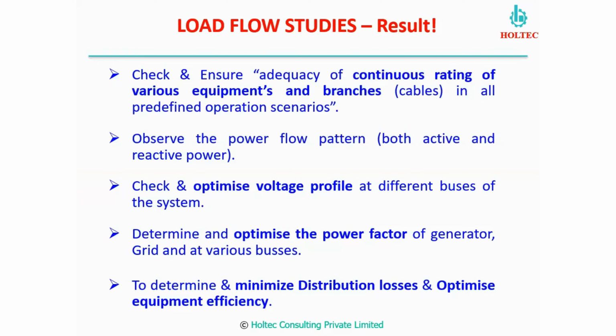Why is this voltage profile optimization required? Actually speaking, with higher voltages the fixed losses increase, because we have mostly inductive loads, whether it is a transformer, a generator or a motor. In inductive loads, the fixed losses or iron losses are proportional to the square of the voltage. So the moment we increase the voltage to its rated value, the fixed losses in this equipment will increase. So if we optimize the voltage, we are able to reduce the fixed losses in the system, especially in the transformers, generators, and motors.